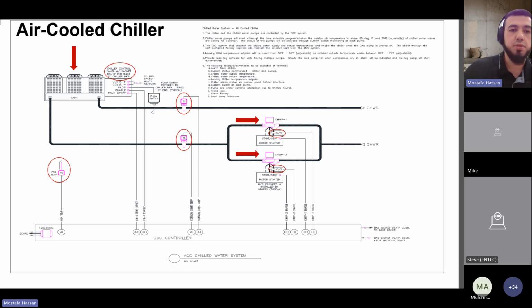The DDC system shall monitor the chilled water supply and return temperatures. There is your chilled water supply, water goes this way, and there's your chilled water return. So there are two temperature sensors on each line. And then it's going to enable the chiller when the chilled water pump is proven on. So there's a condition that the chilled water pump has to be on for the chiller to activate. This is probably a safety to make sure the chiller is not just running for no reason, that the system's actually calling for a chiller.